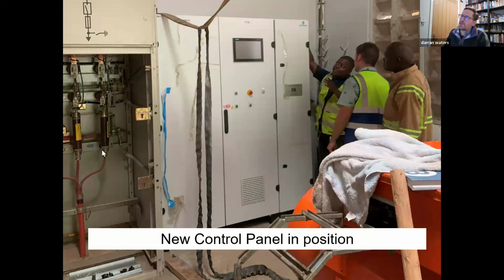You can see inside the switchgear, the existing switchgear here. There was a slight repair we had to make in the mechanism, which wasn't working. So the guys made some new parts to replace the worn ones, so that the switchgear tripped when you opened the door. That way you could isolate it by opening the door, rather than putting your hand inside and operating it like before.